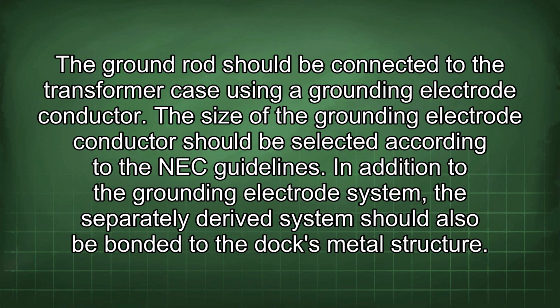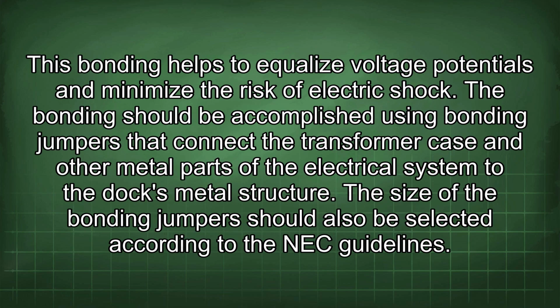In addition to the grounding electrode system, the separately derived system should also be bonded to the dock's metal structure. This bonding helps to equalize voltage potentials and minimize the risk of electric shock. The bonding should be accomplished using bonding jumpers that connect the transformer case and other metal parts of the electrical system to the dock's metal structure. The size of the bonding jumpers should also be selected according to the NEC guidelines.